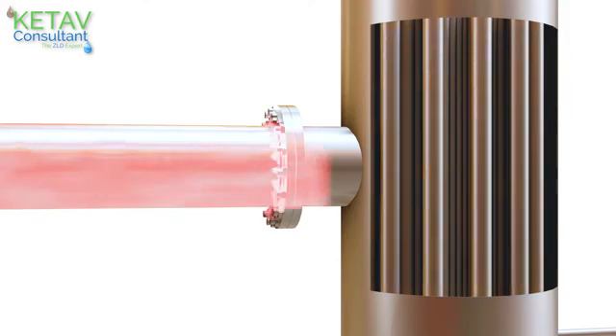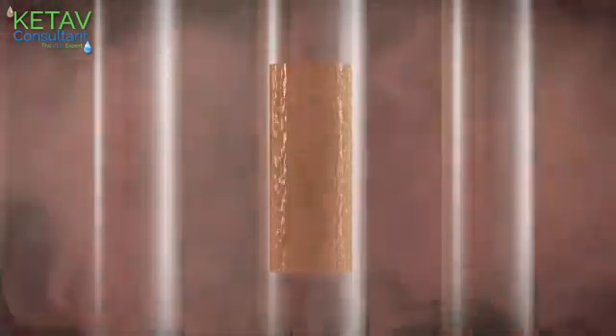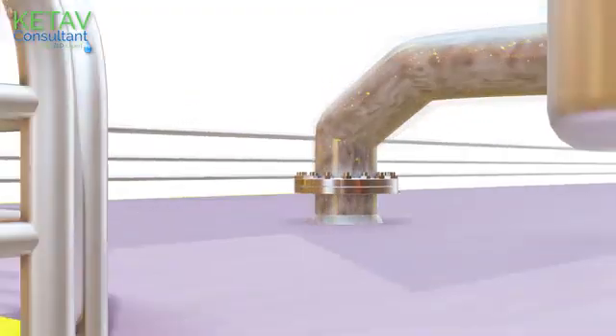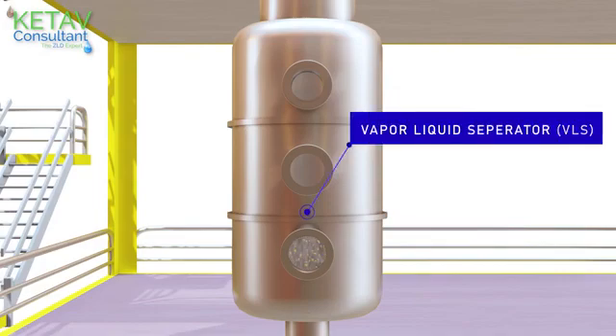To start the evaporation process, external steam is being provided into the shell side of the calandria. Due to conductive heat transfer, steam passes its latent heat to effluent and evaporation of water from the effluent takes place. A water-vapor mixture is being generated which goes to the vapor-liquid separator called VLS.